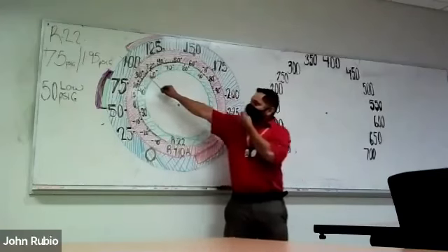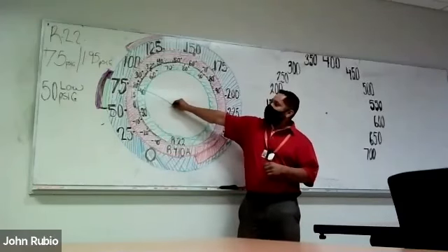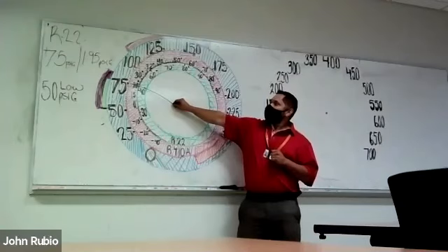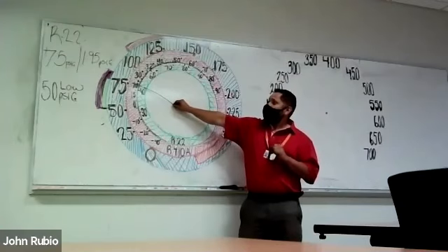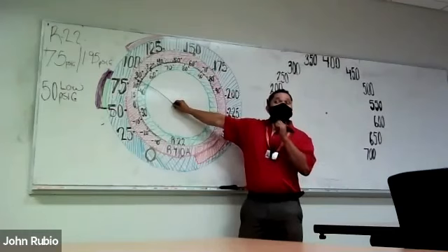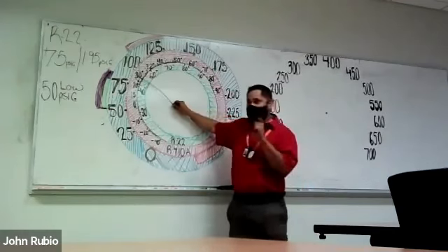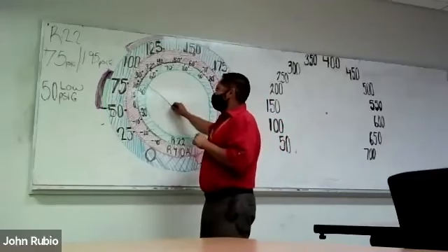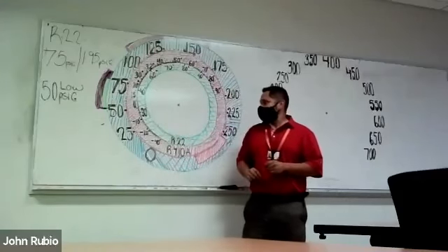We discussed R22 has a low range of 50, high range of 75. The highest I've ever put an R22 unit myself was probably about 81, and this was chasing superheat. I wasn't just charging off gauge pressure. We don't charge off gauge pressure. We charge off superheat.